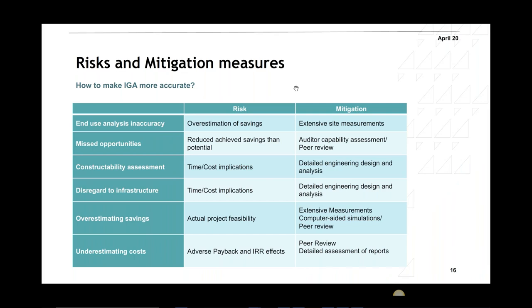Risk and mitigation measures: how to make an IGA more accurate, end use analysis inaccuracy. Overestimation of savings, that's the risk. Mitigation: doing extensive site measurements, and staying on the site for a longer period of time, will give us better visibility on what's happening in our building. Missed opportunities reduce achieved savings below the potential, that's the risk.